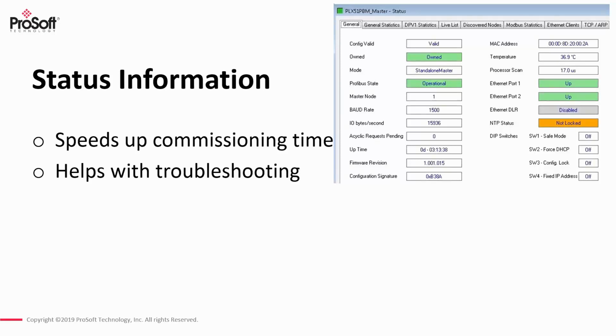It's going to show you overall uptime of the module, as well as firmware revision and some other information. So what we've found over the years in supporting these Profibus applications is that the more status information that can be made available to users, the faster the commissioning time and the easier it is to troubleshoot units. I mean, we all like to think that every project's going to go perfect as we set it up and configure it, but the reality is once you get devices out on the network, there's sometimes issues that occur, and the more status information you can give, the faster we can get those installations up and running.